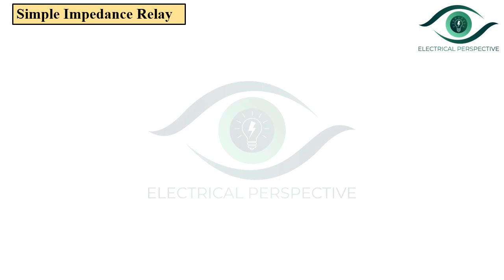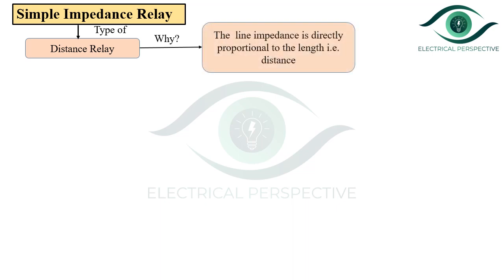Let us start with some basics. Simple impedance relay is a type of distance relay, and we know that the line impedance is directly proportional to the length, that is distance. In other words, impedance is nothing but an electrical measurement of distance along the transmission line, and thus it is also called a distance relay.